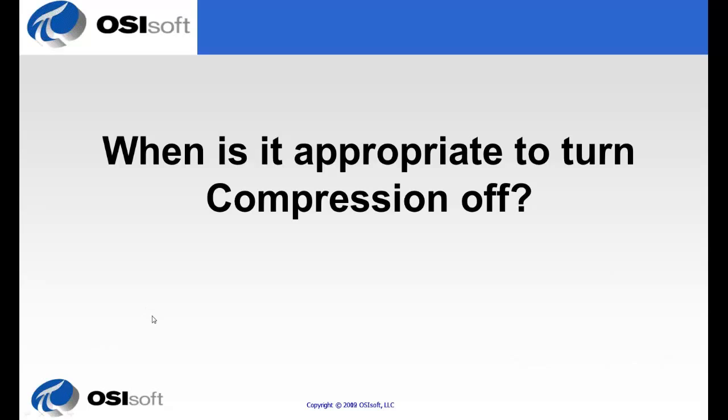When is it appropriate to turn compression off? OSIsoft generally recommends not ever turning off compression. However, it is appropriate for a few scenarios. For laboratory values or manually entered values or totalized points where every value is significant, it may be appropriate to turn compression off. Also, there may be government requirements regarding data collection that require disabling compression. If you set compression to off, then all exceptions are archived.